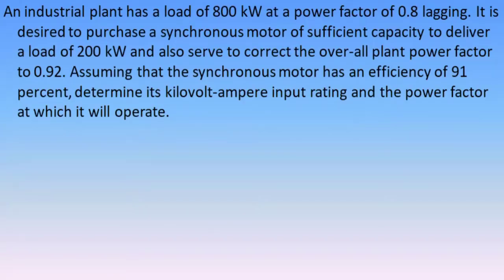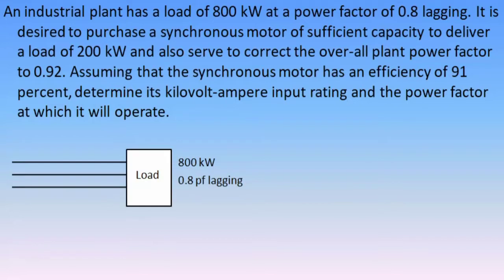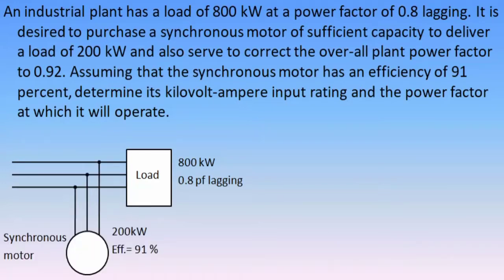Now let's try to understand the problem. We have an industrial plant initially has a load of 800 kilowatts at a power factor of 0.8 lagging. In order to correct the power factor to 0.92, a synchronous motor is to be purchased. This synchronous motor will be delivering a load of 200 kilowatts, and it is assumed that this motor has an efficiency of 91%.